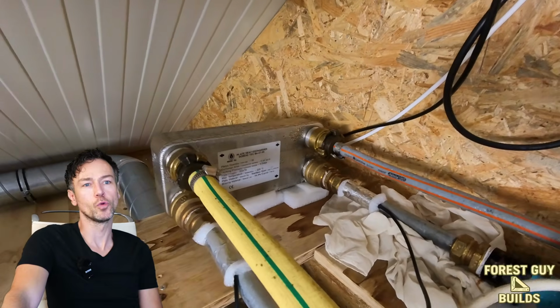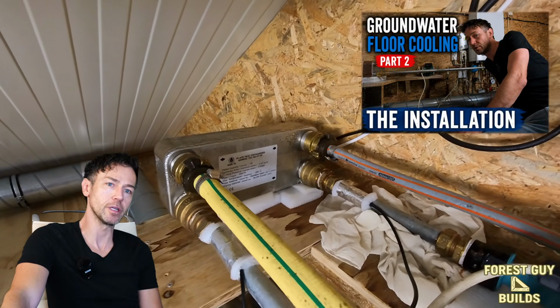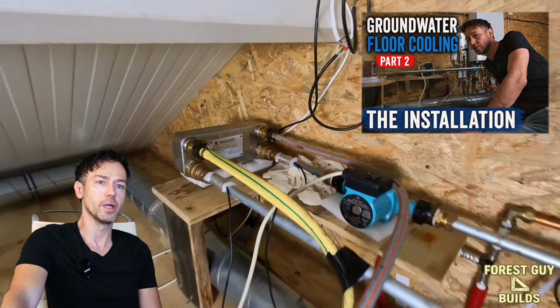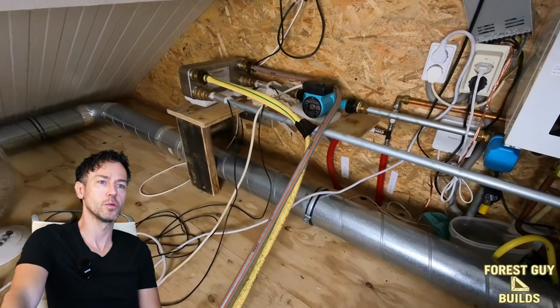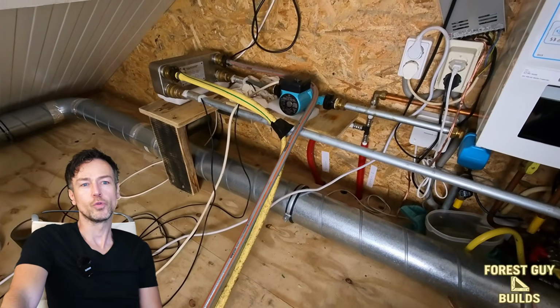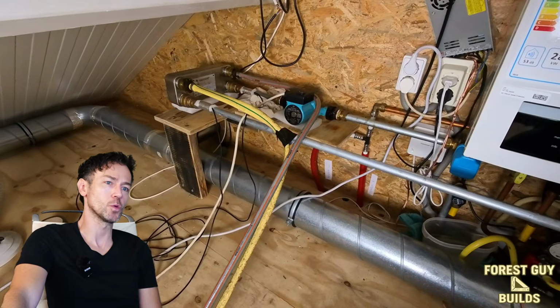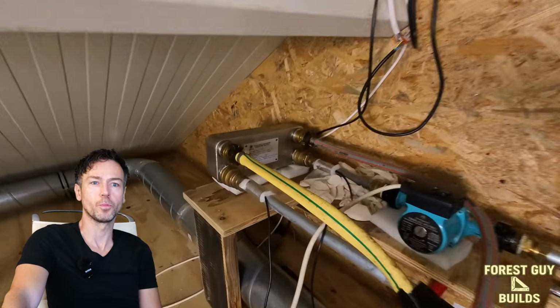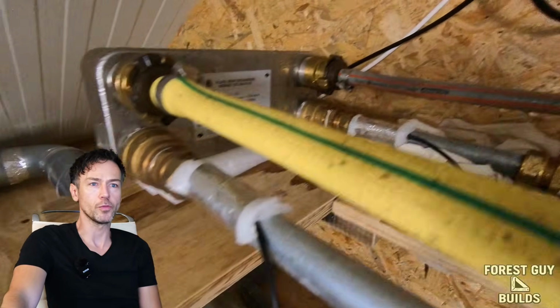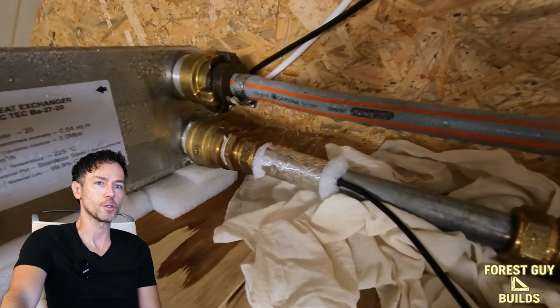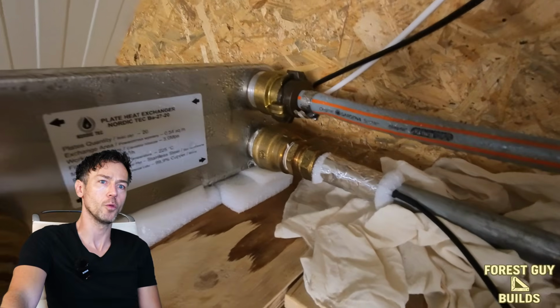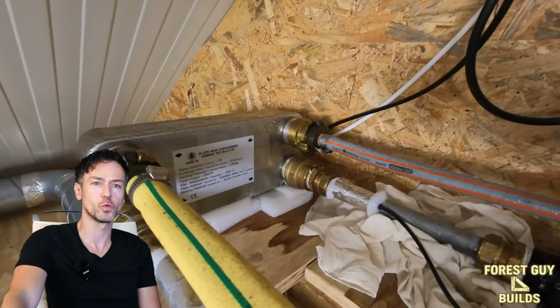This is the actual cooling setup which I explained in more detail in the previous video. What's worth mentioning now are the things I discovered during the first days of real cooling. To get some insight into what is happening, I installed temperature sensors directly onto the pipes. They show me the supply and return temperature of the floor cooling circuit, telling me exactly how much the water is warming up as it moves through the floor.